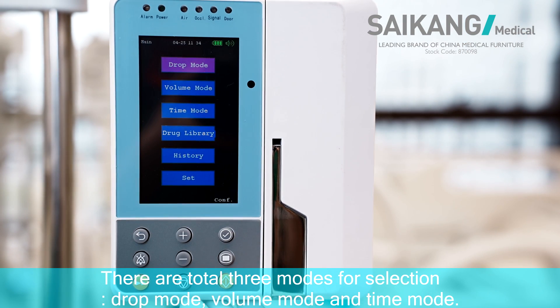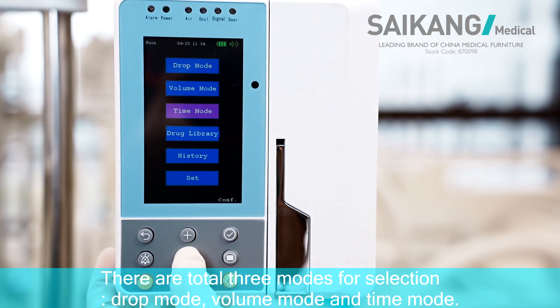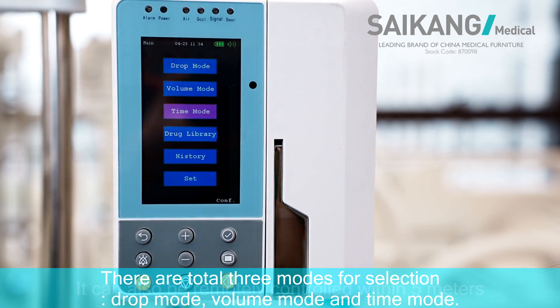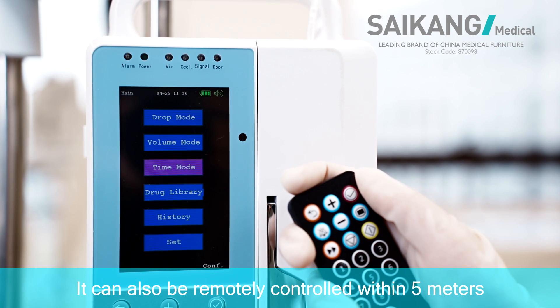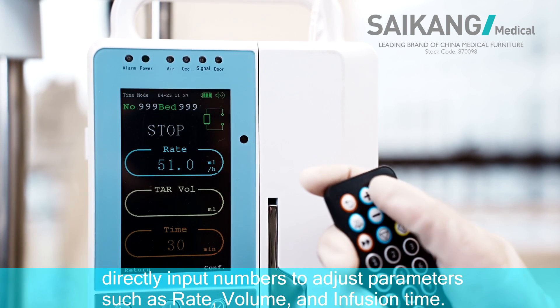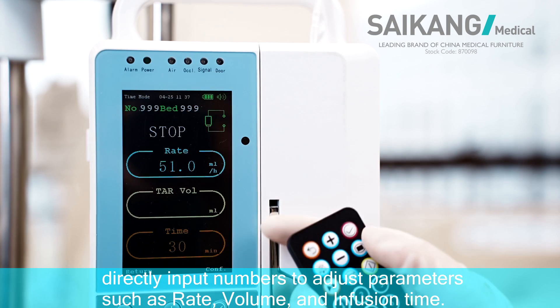There are a total of three modes for selection: drop mode, volume mode, and time mode. It can also be remotely controlled within 5 meters. We can directly input numbers to adjust parameters such as the rate, volume, and infusion time.